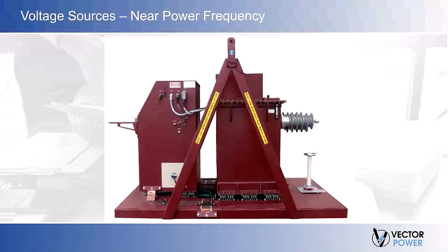Let's move on to near power frequency, sinusoidal voltage sources. These can replicate the waveform of the operating voltage in the device under test system and allow for increased voltage magnitudes beyond the normal operating levels.